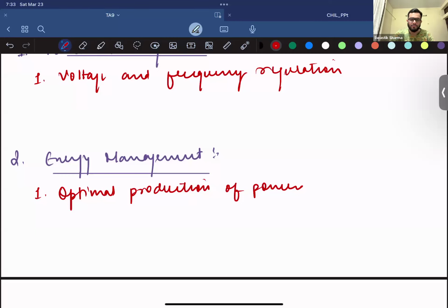Battery energy storage always works in tandem with the supercapacitor. There's a reason why: batteries are low power density devices. Even though they can store a large amount of energy, the rate at which they can provide this energy is low. So let's say your system's real power is suddenly collapsing. The BESS can start changing their real time power generation accordingly, but your supercapacitors can pitch in. They have low energy density, they don't store a lot of energy, but they have high power density, so they can quickly provide power to the system.